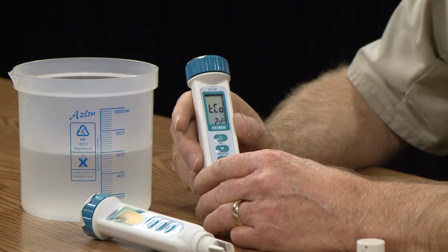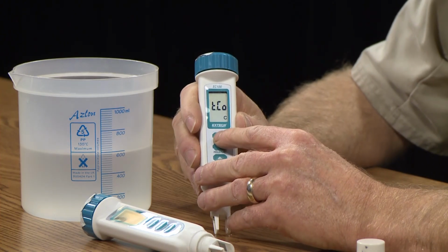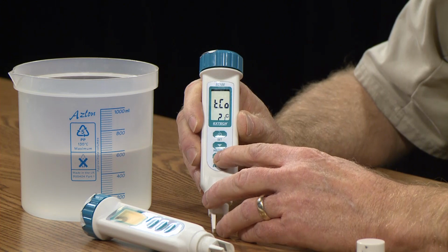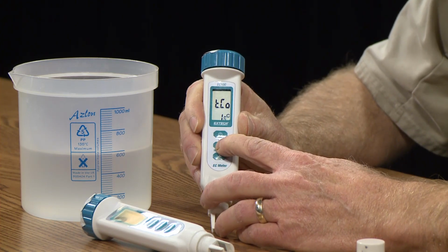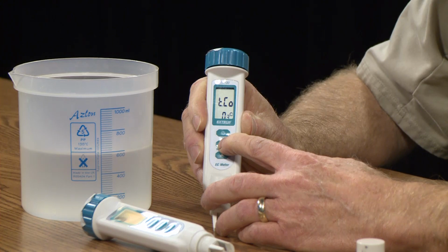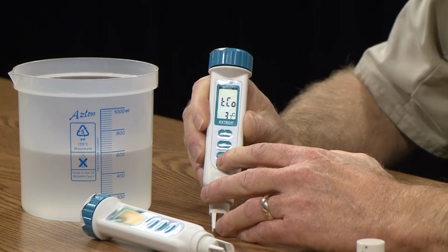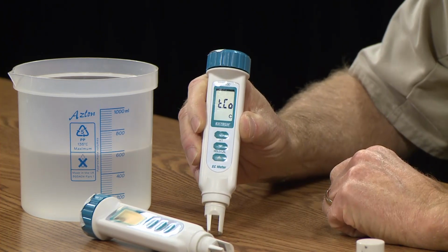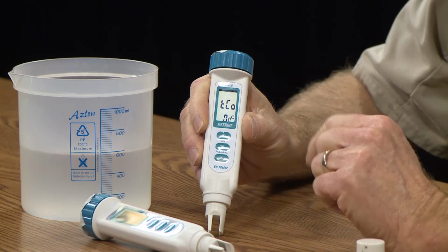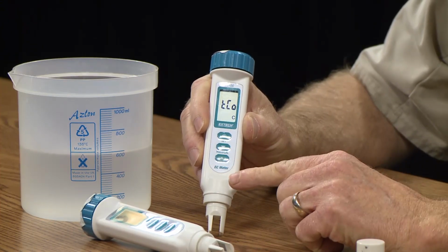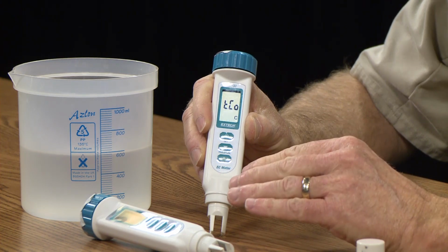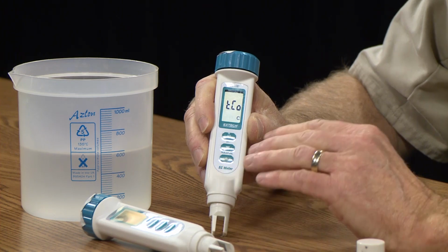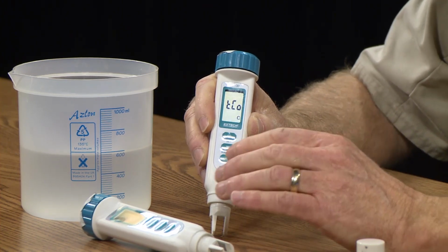So now, wonder if I take this adjustment factor and take it down to 0. Whoop, going the wrong way, 2.1. I'm just going to take it down to 0. Whoop, yeah, went the other way. How you like that? Didn't realize I'd do that. Okay, 0.0. So that's the adjustment factor. So both of these conductivity meters are now set at no adjustment factor. So they both will be giving me the raw conductivity reading, that is the ambient conductivity reading, unadjusted for temperature.